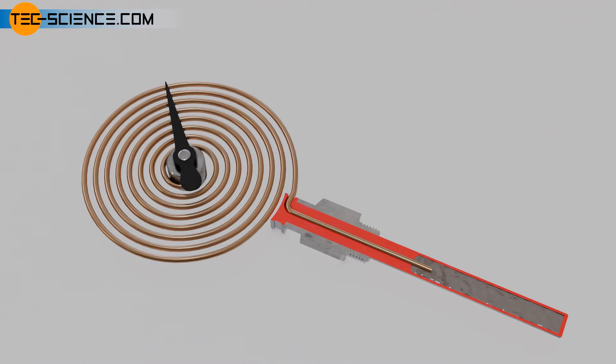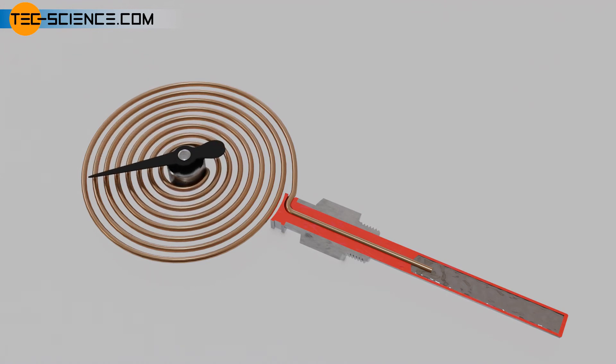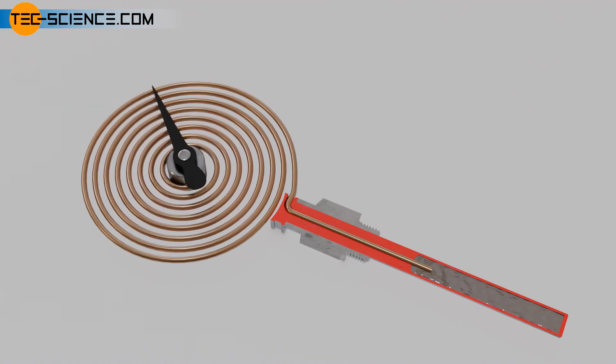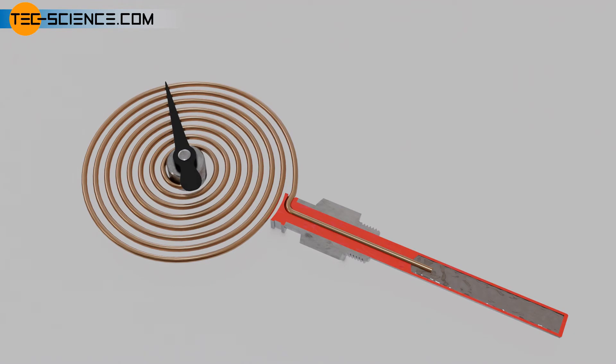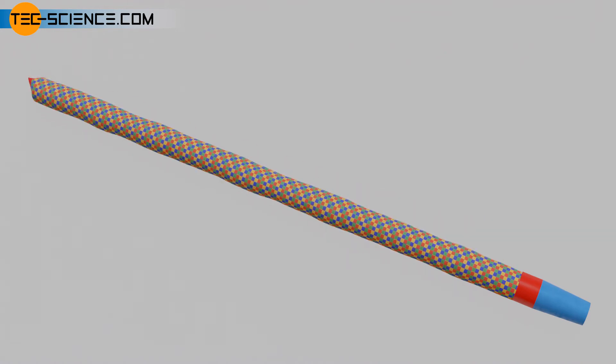The elastic deformation of the tube at a temperature increase is directly applied to a rotatively mounted pointer. The corresponding temperature can then be read off from a calibrated scale. The working principle of the Bourdon tube is similar to that of a party horn at children's birthday parties, in which a rolled-up paper tube is bent up by increasing the pressure inside.